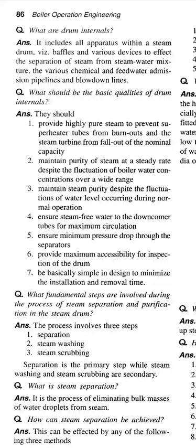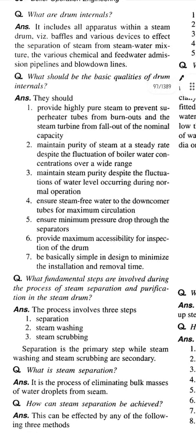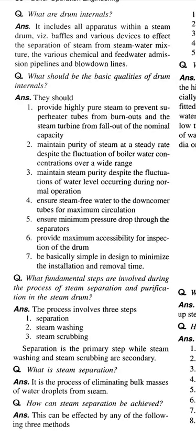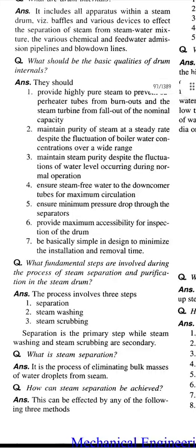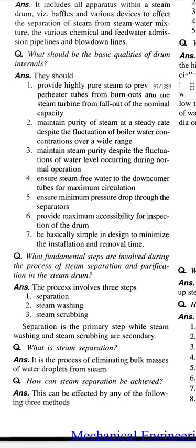Ensure steam-free water to downcomer tubes for maximum circulation. Ensure minimum pressure drop through the separators. Provide maximum accessibility for inspection of the drum. Be basically simple in design to minimize the installation and removal time. The question: what fundamental steps are involved during the process of steam separation and purification in the steam drum?